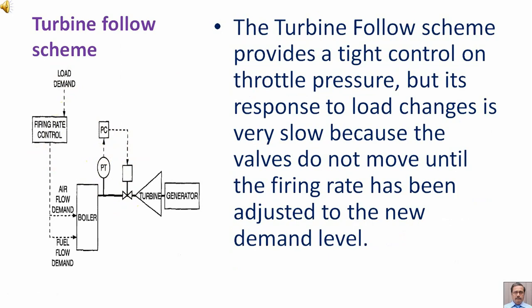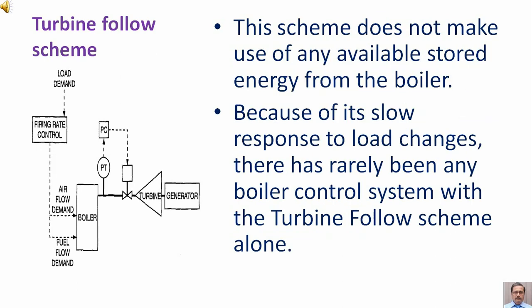The turbine follow scheme provides tight control on throttle pressure, but its response to load changes is very slow, because the valves do not move until the firing rate has been adjusted to the new demand level. This scheme does not make use of any available stored energy from the boiler. Because of its slow response to load changes, there has rarely been any boiler control system with the turbine follow scheme alone.